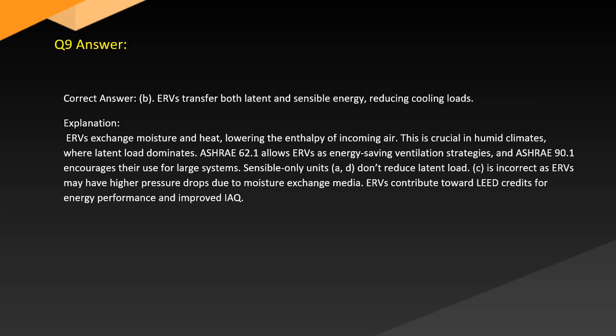Answer. Correct answer B. ERVs transfer both latent and sensible energy, reducing cooling loads. Explanation. ERVs exchange moisture and heat, lowering the enthalpy of incoming air. This is crucial in humid climates where latent load dominates. ASHRAE 62.1 allows ERVs as energy-saving ventilation strategies, and ASHRAE 90.1 encourages their use for large systems.